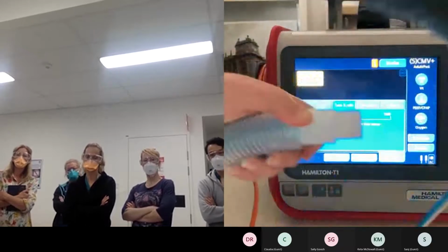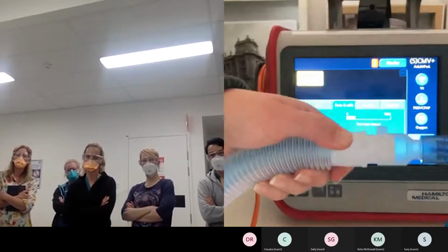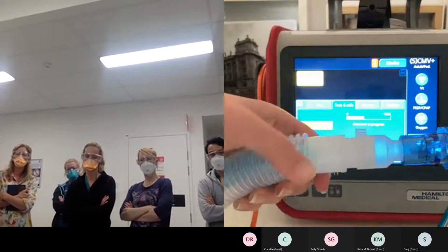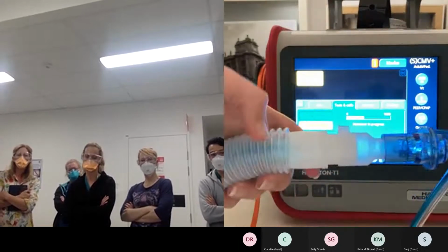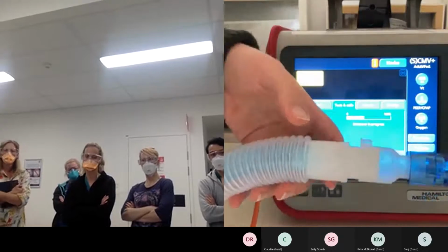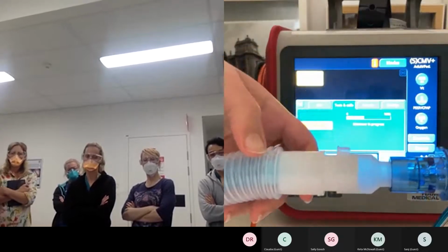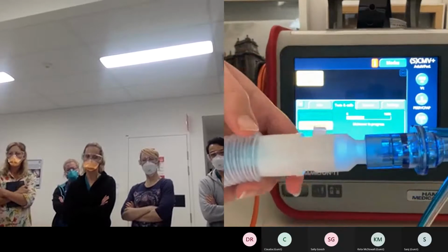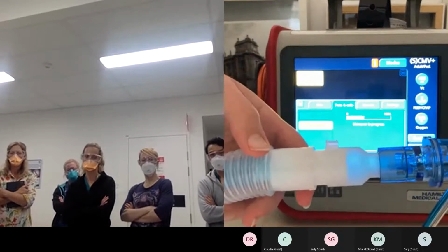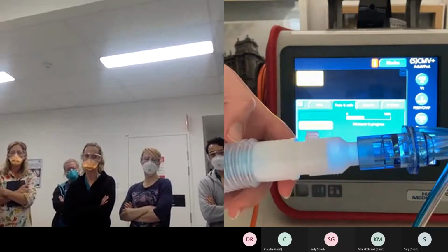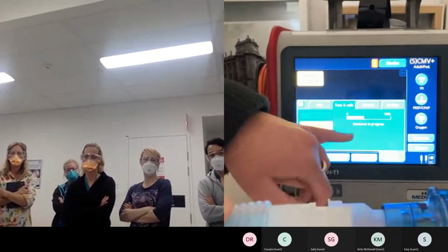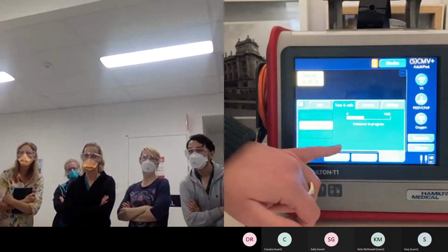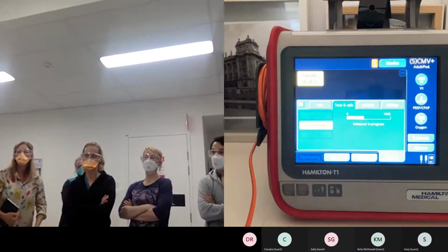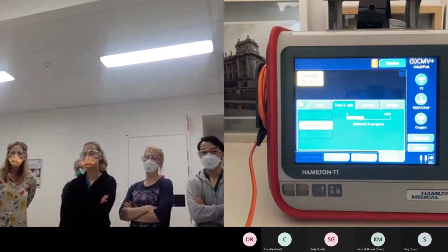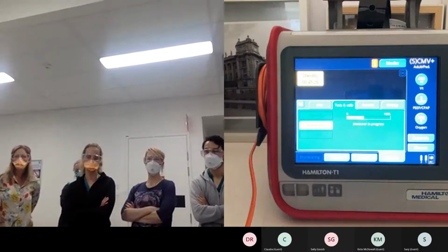And then turn flow sensor. So take hold of the blue and turn the whole thing around. Okay. What it will do as part of this process is it blows 5 preset levels of flow through. So it measures it at each of those points. And then it sounds like it ramps up, and then will almost sound like it cuts out. And you'll get a message on the screen. So at the moment, I don't know if you can see it, it says maneuver in progress. When it's ready to turn, it will tell you turn flow sensor.